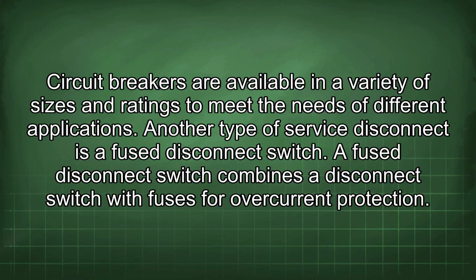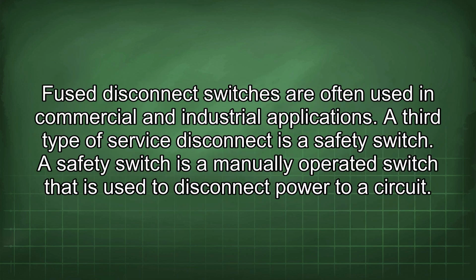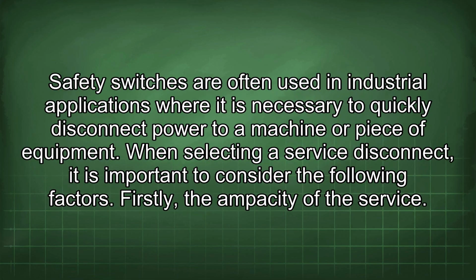Another type of service disconnect is a fuse disconnect switch. A fuse disconnect switch combines a disconnect switch with fuses for overcurrent protection. Fuse disconnect switches are often used in commercial and industrial applications. A third type of service disconnect is a safety switch. A safety switch is a manually operated switch that is used to disconnect power to a circuit. Safety switches are often used in industrial applications where it is necessary to quickly disconnect power to a machine or piece of equipment.